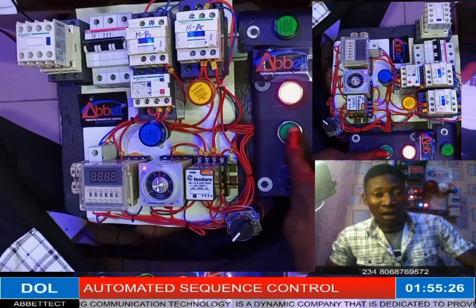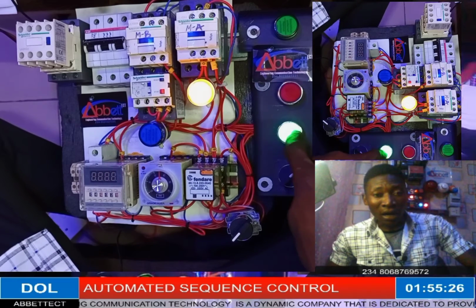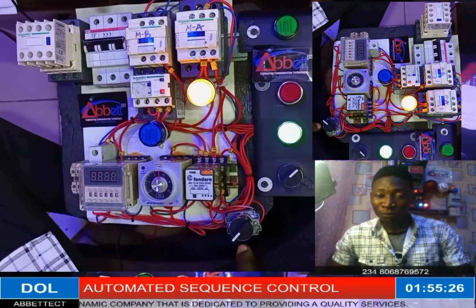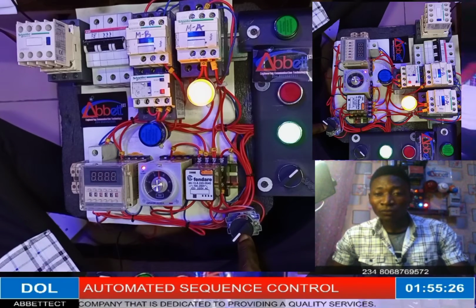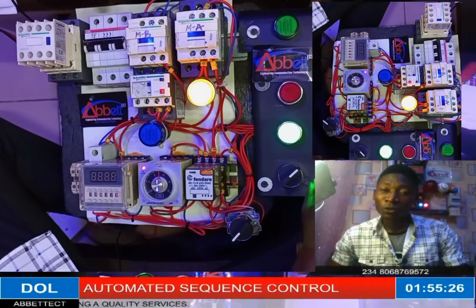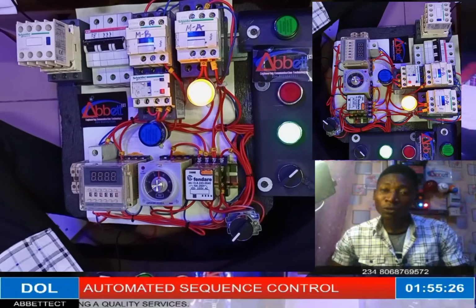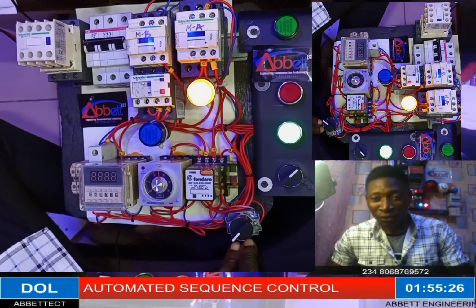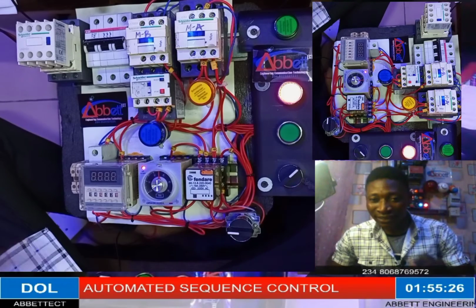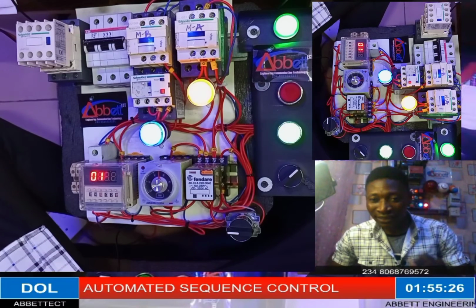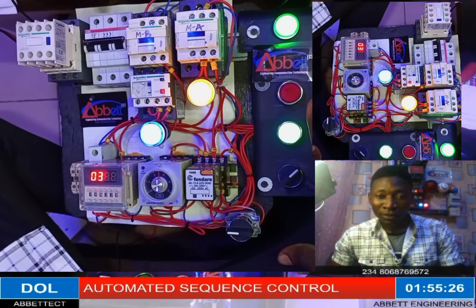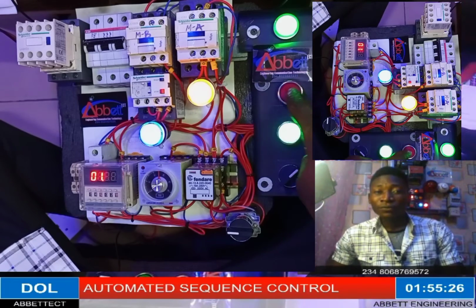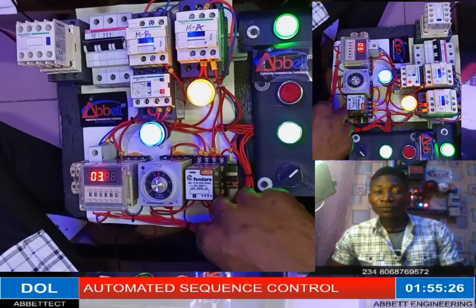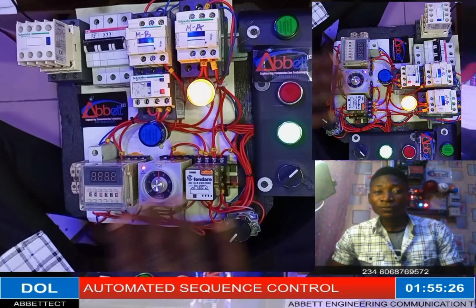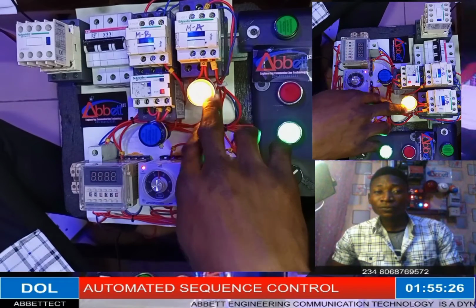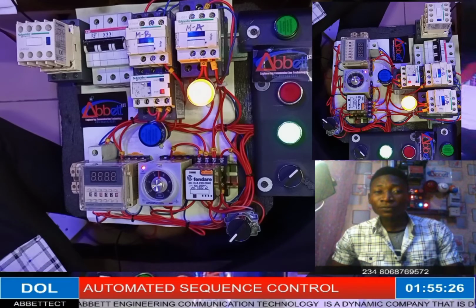Without starting, you see now, it can't hold because it's on auto. You understand? The system cannot hold. You see it. It cannot hold because it's on automatic. Let's put it in manual now. You see now, this is different. This is manual now. I'm operating manually. You see it's operating. So let's put it on auto. It's on auto now. It cannot hold, but the delay time will still operate as it used to.